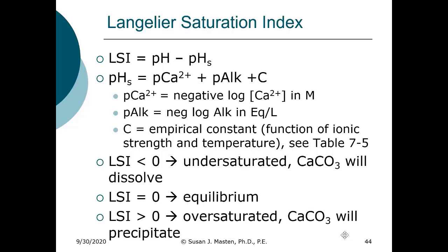So one of the methods that we use to assess this is referred to as the Langelier saturation index. It is really a measure of the degree to which a water is saturated with respect to calcium carbonate. So we use what is referred to as pHs, the pH saturation, and that is equal to the negative log of the calcium concentration, and we need that in molar units.